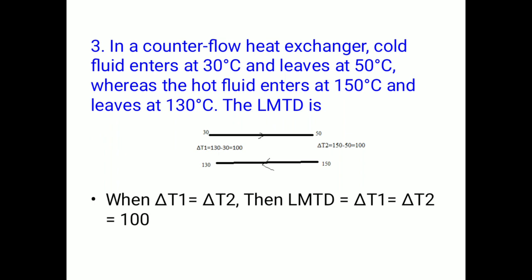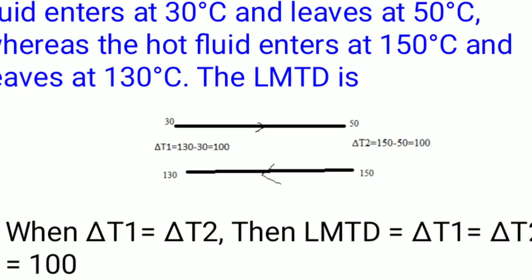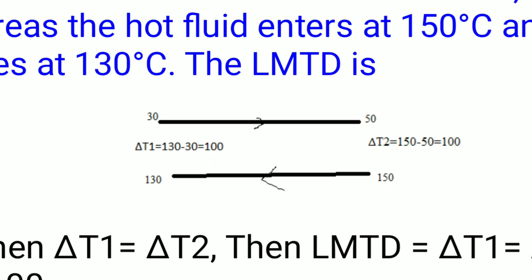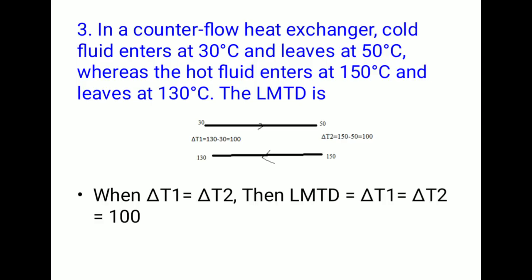Numerical 3: In a counter-flow heat exchanger, the cold fluid enters at 30°C and leaves at 50°C, while the hot fluid enters at 150°C and leaves at 130°C. Delta T1 = 130 − 30 = 100°C and delta T2 = 150 − 50 = 100°C. When delta T1 equals delta T2, LMTD equals delta T1 = delta T2 = 100°C.